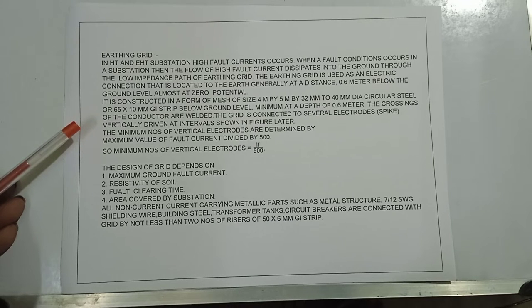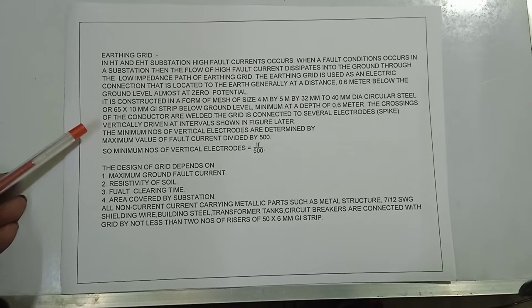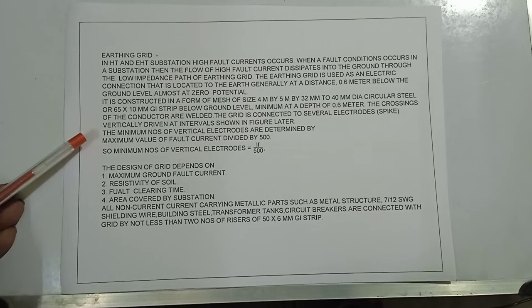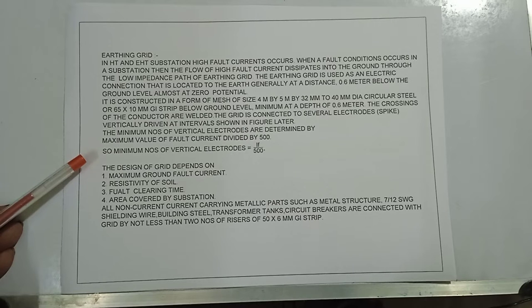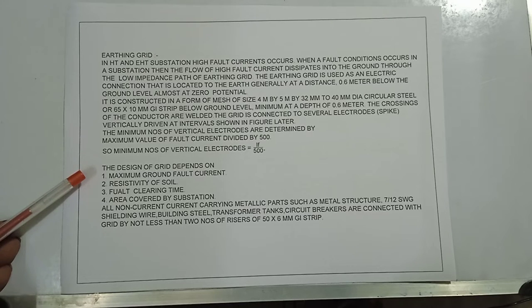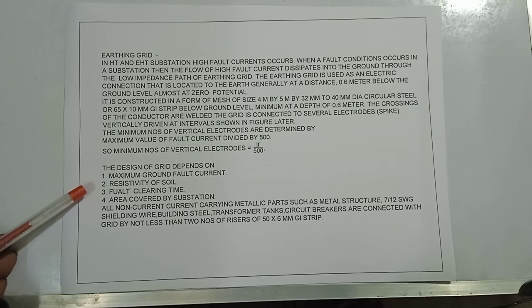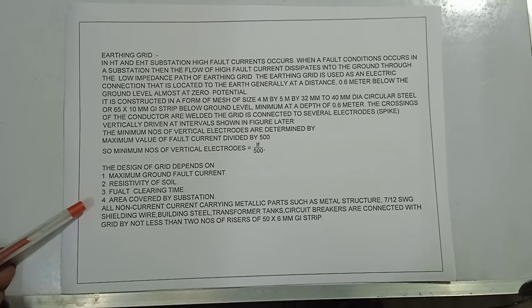The grid is connected to several electrodes spiked vertically at intervals. The minimum number of vertical electrodes is determined by: minimum electrodes = If / 500. The design of the grid depends on: (1) maximum ground fault current, (2) resistivity of soil, (3) fault clearing time, and (4) area covered by the substation.